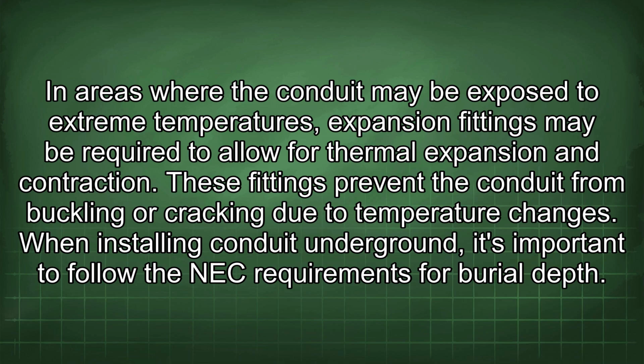In areas where the conduit may be exposed to extreme temperatures, expansion fittings may be required to allow for thermal expansion and contraction. These fittings prevent the conduit from buckling or cracking due to temperature changes.